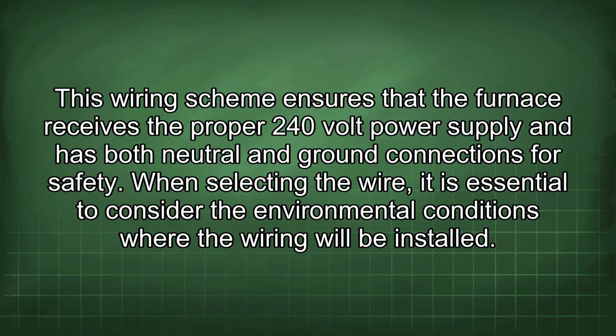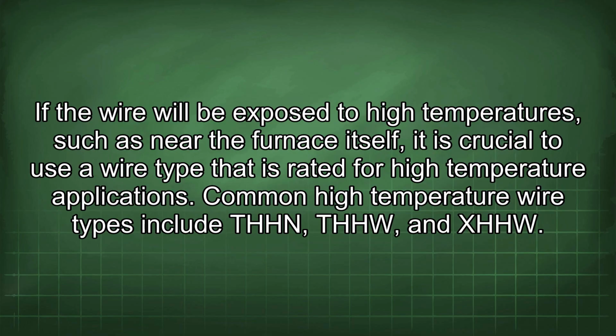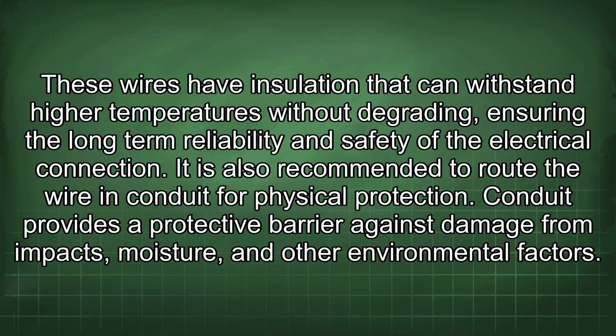When selecting the wire, it is essential to consider the environmental conditions where the wiring will be installed. If the wire will be exposed to high temperatures, such as near the furnace itself, it is crucial to use a wire type that is rated for high temperature applications. Common high temperature wire types include THHN, THHW, and XHHW. These wires have insulation that can withstand higher temperatures without degrading, ensuring the long-term reliability and safety of the electrical connection.